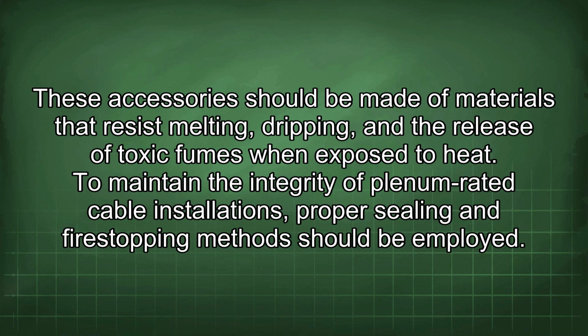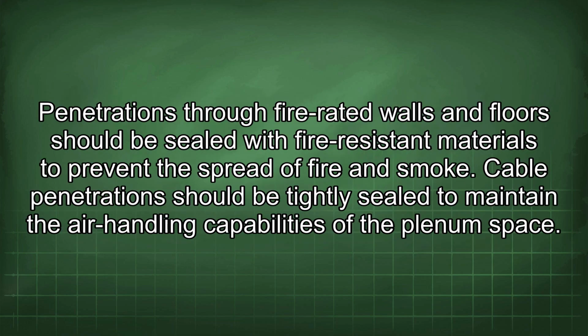To maintain the integrity of plenum-rated cable installations, proper sealing and fire-stopping methods should be employed. Penetrations through fire-rated walls and floors should be sealed with fire-resistant materials to prevent the spread of fire and smoke. Cable penetrations should be tightly sealed to maintain the air handling capabilities of the plenum space.